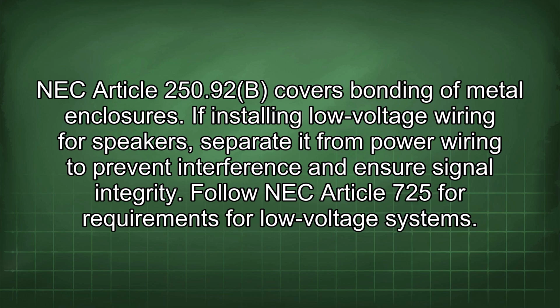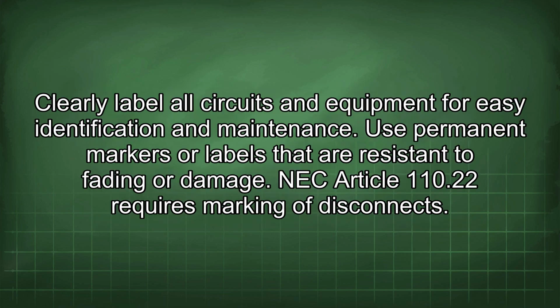If installing low-voltage wiring for speakers, separate it from power wiring to prevent interference and ensure signal integrity. Follow NEC Article 725 for requirements for low-voltage systems. Clearly label all circuits and equipment for easy identification and maintenance. Use permanent markers or labels that are resistant to fading or damage. NEC Article 110.22 requires marking of disconnects.